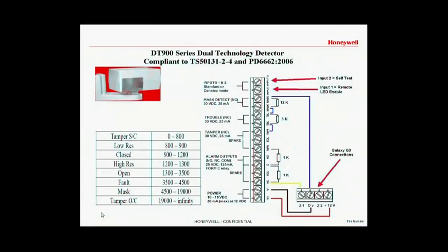If the detector, like a Honeywell DT900 series, has the separate mask, trouble, tamper and alarm outputs, then 1K is a closed. In an alarm condition we read 2K. In a fault condition we read 4K. And in a mask condition we read 13K.